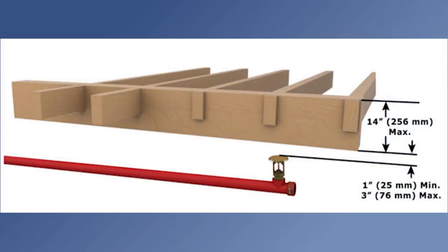Yeah, we offer our VK467 4.9 K-factor residential upright sprinkler. And we were just talking about how listings kind of went away for residential sprinklers. Well, that's in most situations, but with this sprinkler, we have a special beam listing for the VK467 because of what you just described. That's the type of area that the sprinkler would commonly be installed in.